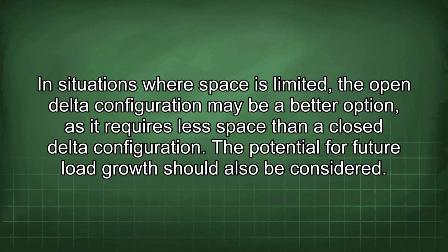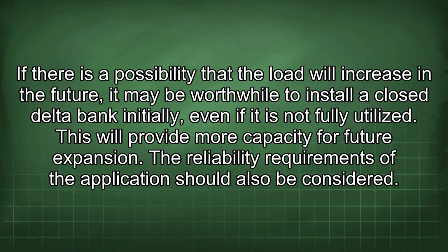The potential for future load growth should also be considered. If there is a possibility that the load will increase in the future, it may be worthwhile to install a closed delta bank initially, even if it is not fully utilized. This will provide more capacity for future expansion.